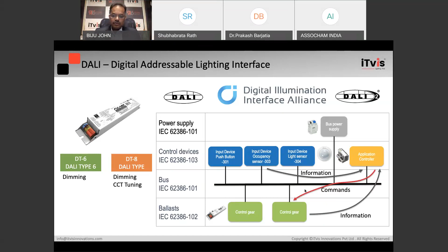Normally the length of the DALI bus is limited to 300 meters. If you are using DALI in a building management system or lighting management system, I think KNX can even go up to 350 meters. That's the maximum, and the DALI bus is used only up to 300 meters. Of course, there is a provision: you can go for DALI repeaters if you want to take the length of the DALI bus beyond 300 meters. DALI repeaters are also available. Now, you don't need to get confused; I'm making it very simple in explaining the DALI lighting management system.